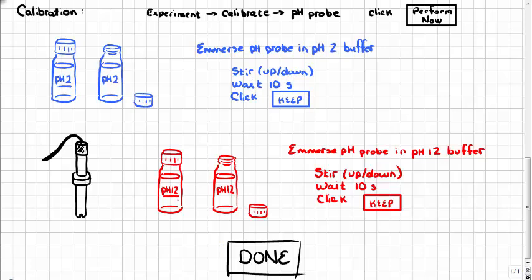The reason we're using such broad-spaced pHs for calibration purposes is because we would like the pH probe to be accurate over a fairly broad range, as the pHs that we're going to measure today will be both acidic and quite basic. We're going to go for the broadest calibration possible, although truth be told, if you were really interested in accurate pH measurements, you would certainly calibrate it over a tighter range. But this broad range will suffice for us here today.